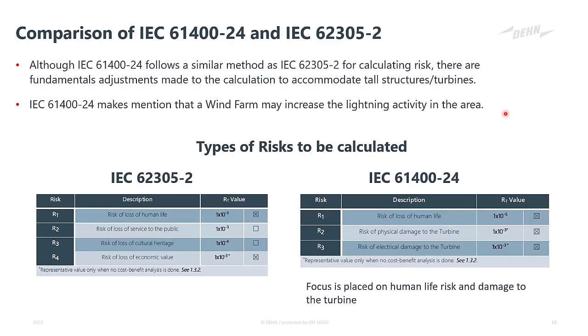So after building a wind farm, you will see that there's more lightning within that area. If we then calculate risks according to the standard for buildings, there are 4 risks that we typically calculate. The one being loss of human life, dangers to human life. We could also calculate loss of service to the public. So if it's something like electricity supply, water supply, public service, we want to calculate if there's a risk that the public would be without that service.